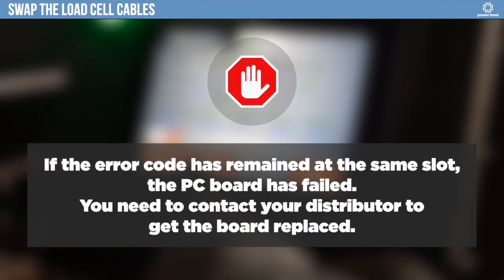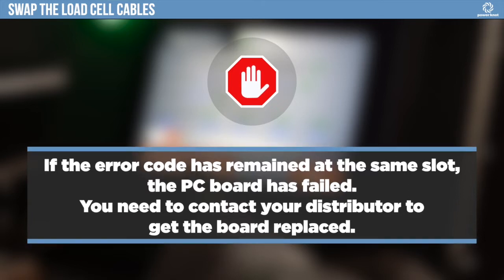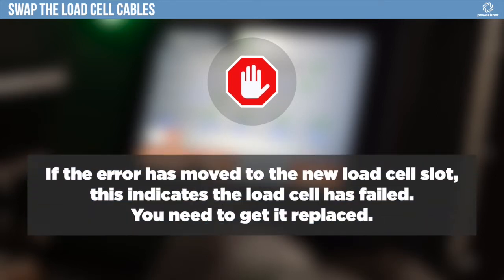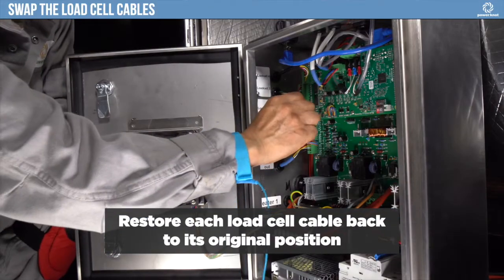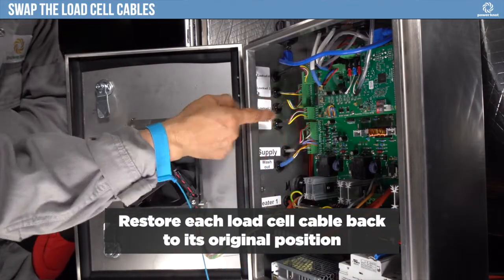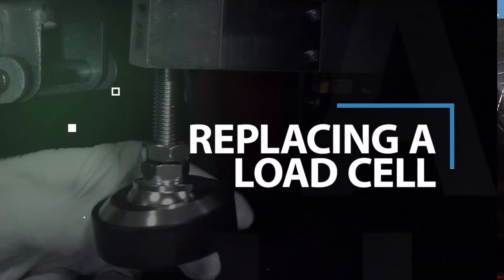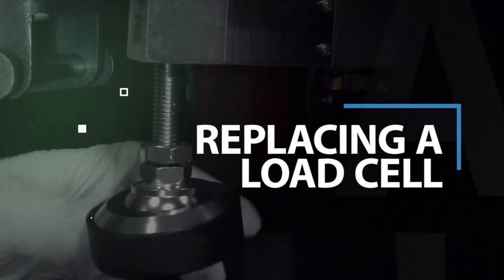If the error code has remained at the same slot, the PC board has failed. You need to contact your distributor to get the board replaced. If the error has moved to the new load cell slot, this indicates the load cell has failed. You need to get it replaced. Restore each load cell cable back to its original position. Here are the steps to replace a load cell.